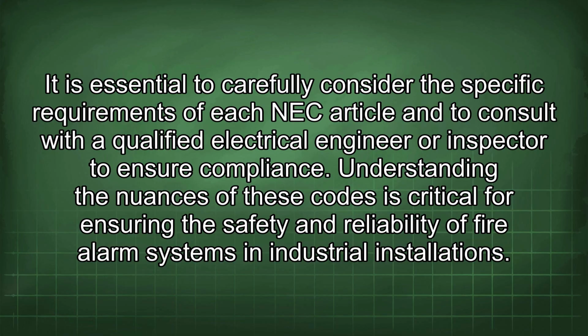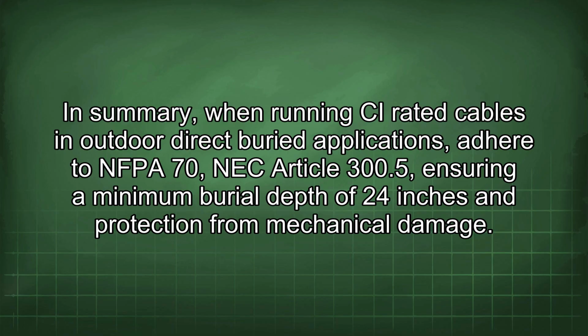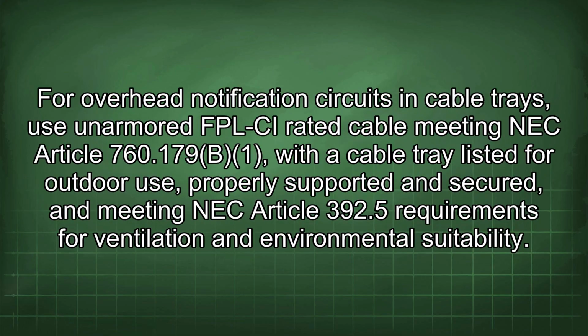Understanding the nuances of these codes is critical for ensuring the safety and reliability of fire alarm systems in industrial installations. In summary, when running CI-rated cables in outdoor direct buried applications, adhere to NFPA 70, NEC Article 300.5, ensuring a minimum burial depth of 24 inches and protection from mechanical damage. For overhead notification circuits in cable trays, use unarmored FPL-CI rated cable meeting NEC Article 760.179 with a cable tray listed for outdoor use, properly supported and secured, and meeting NEC Article 392.5 requirements for ventilation and environmental suitability.